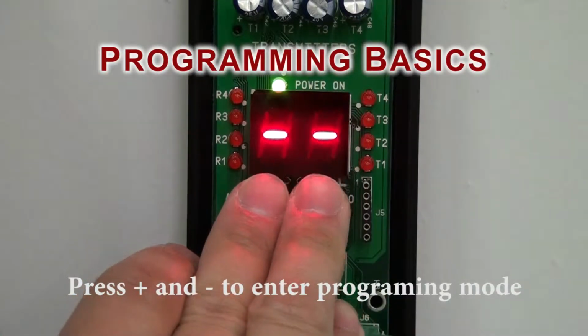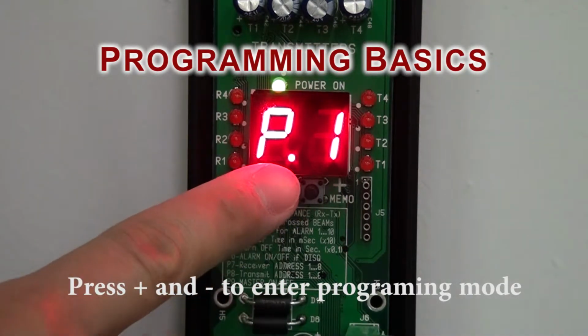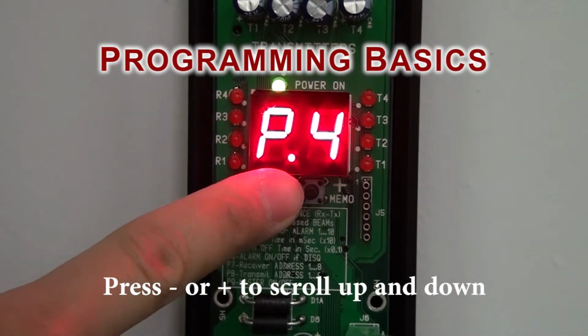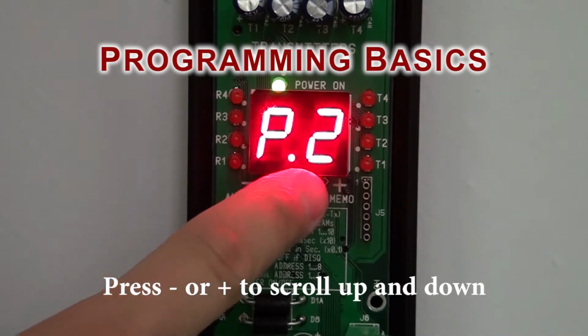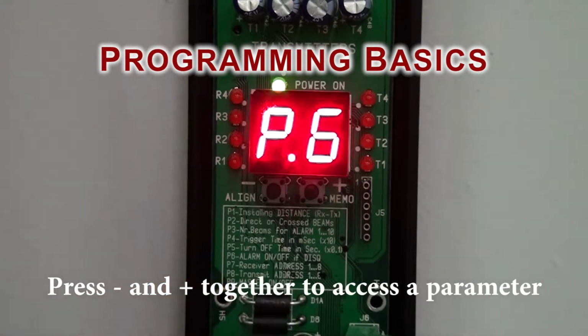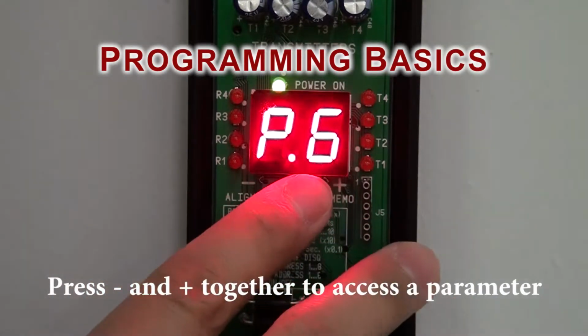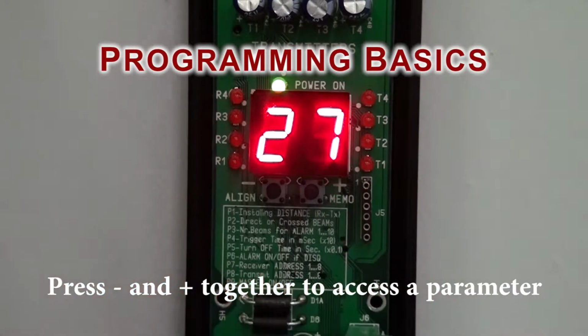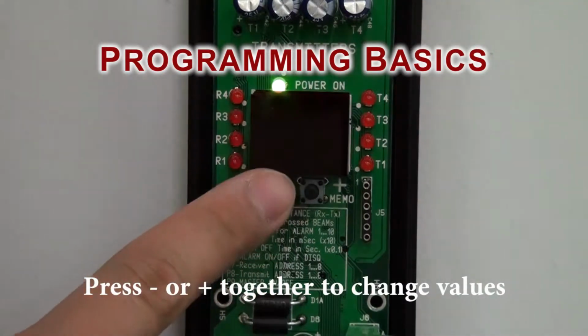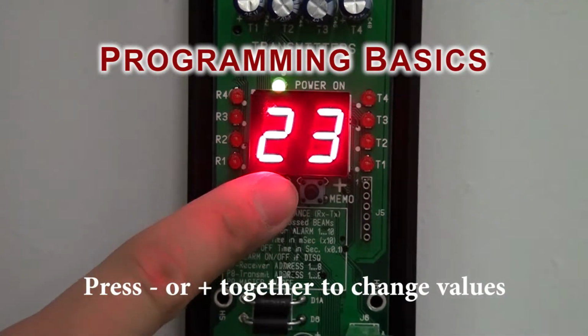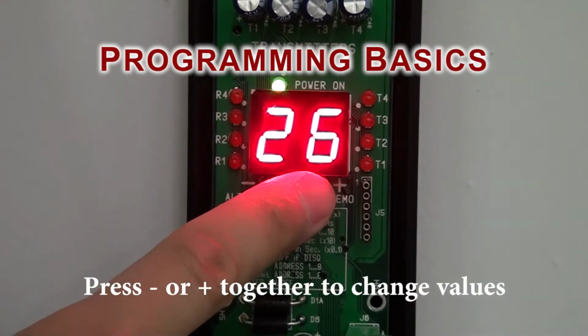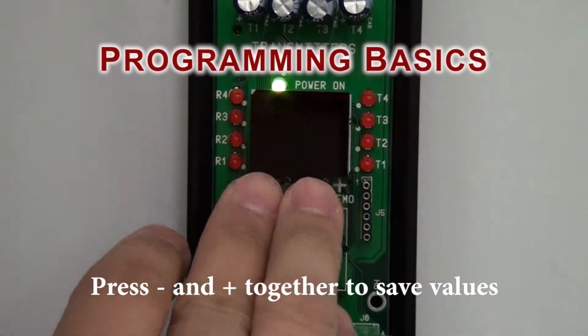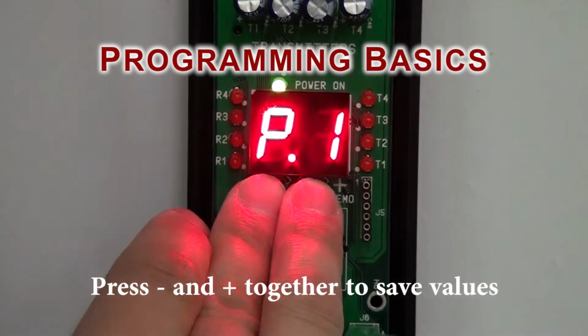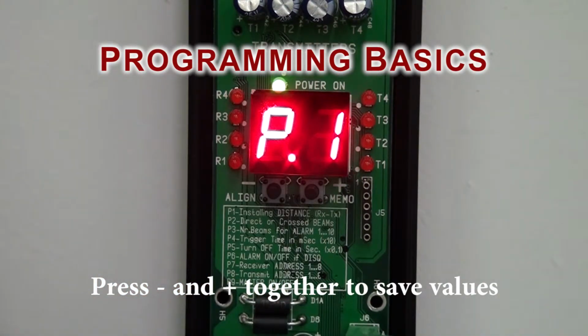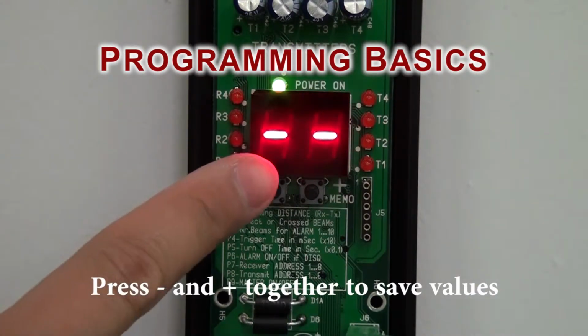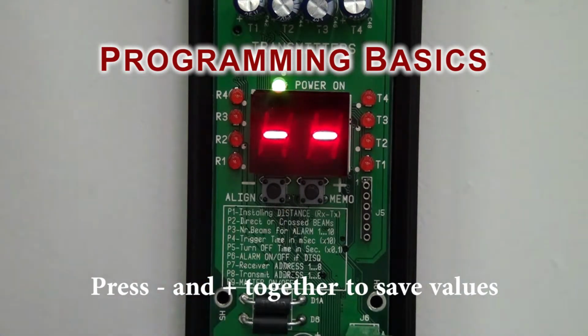Pressing both buttons together will display parameter P1. From P1 you can press minus or plus to access parameters P1 through P6. To alter parameters, say P1, press plus and minus together again to access the value. Once you access the parameters, press minus or plus to change the value. Once you have your value set, press minus and plus together to save and exit the parameter. Parameters will exit after 3 seconds of inactivity, or you can also hold the button down.